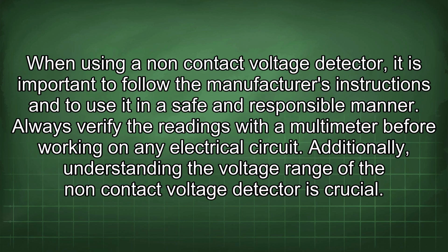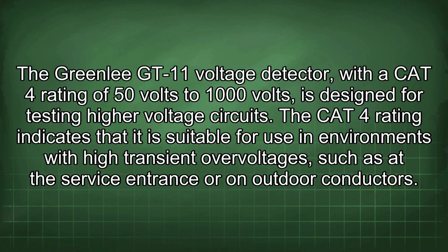When using a non-contact voltage detector, it is important to follow the manufacturer's instructions and to use it in a safe and responsible manner. Always verify the readings with a multimeter before working on any electrical circuit. Additionally, understanding the voltage range of the non-contact voltage detector is crucial. The Greenlee GT-11 voltage detector, with a CAT4 rating of 50 volts to 1000 volts, is designed for testing higher voltage circuits. The CAT4 rating indicates that it is suitable for use in environments with high transient overvoltages, such as at the service entrance or on outdoor conductors.